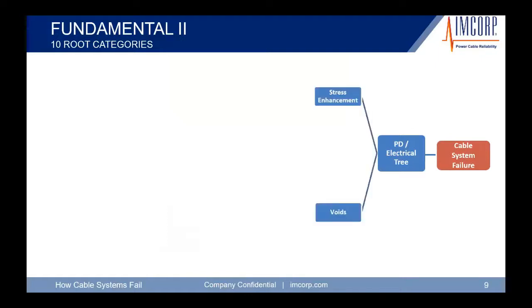So what causes faults in medium voltage cables and high voltage cables? We have electrical trees, which are partial discharge. There's two different categories that we have. We have stress enhancements and we have voids.